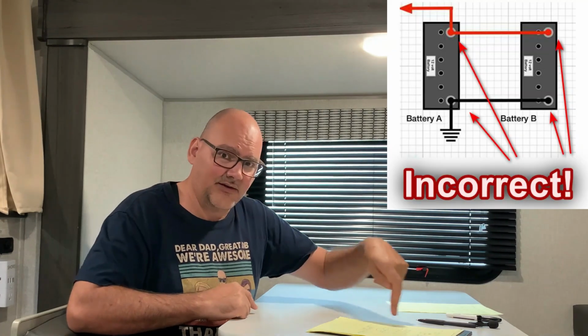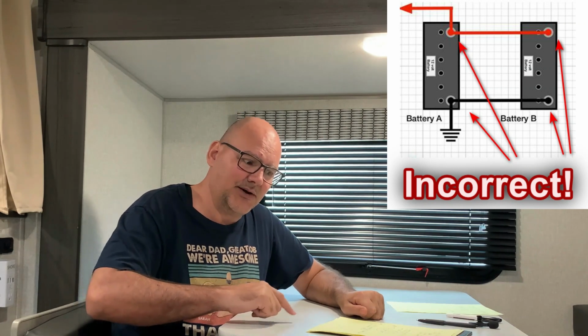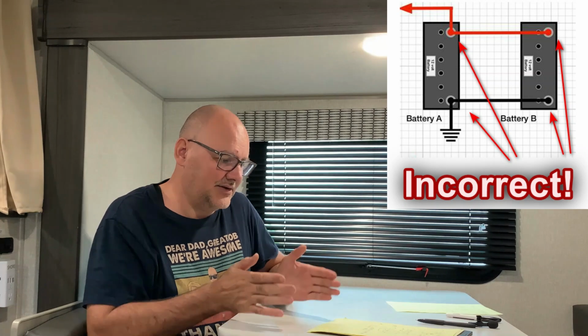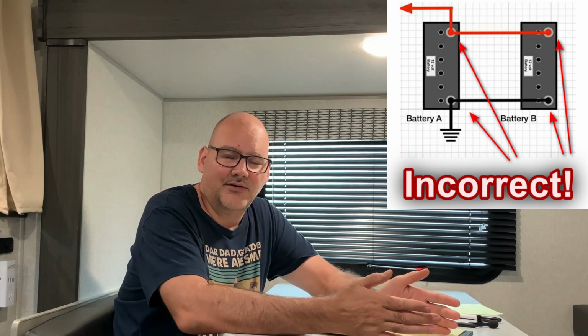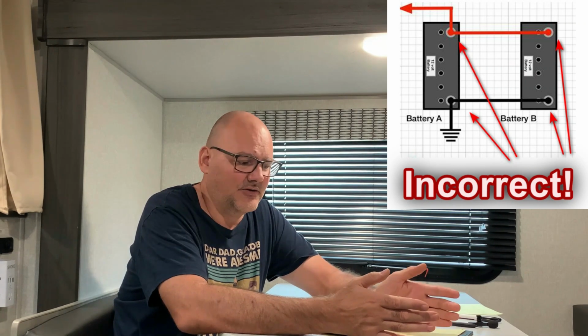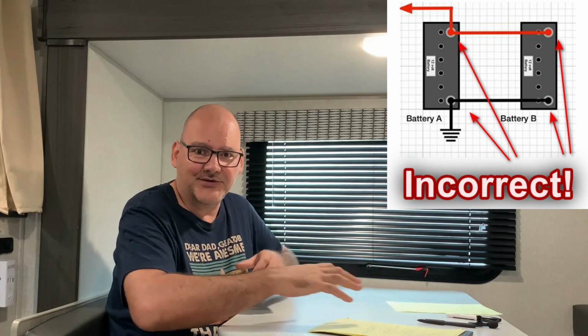Another issue is whenever you're running multiple batteries and tying them together, you're tying them negative, negative, negative, negative all the way down the line, and then going out, then positive, positive, positive, positive, and going out. This is actually bad because the end batteries on that set are going to have a lower discharge and lower charging rate. Each battery is going to have a less equal charging experience. So this one may charge and discharge fully each cycle, while this one may not, and it's going to make your batteries wear out incorrectly. You're going to have one battery that's dead while another may still have 50% of life left, and you'll end up having to replace all your batteries thinking they're all shot.